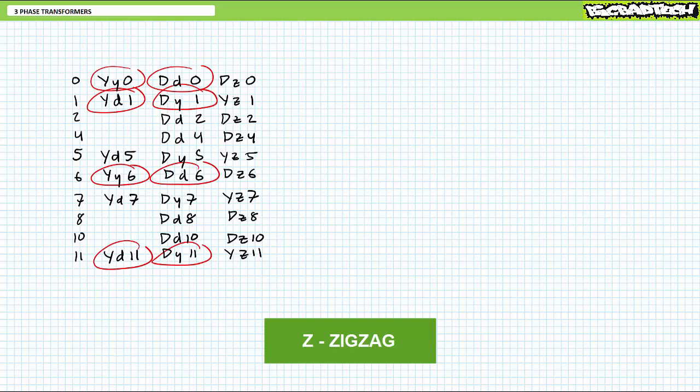Zigzags are kind of like Ys, or if you're an idiot, stars, only they have double the number of windings for each phase such that if you're super, super desperate for a super weird phase shift or an odd voltage magnitude, or you just want to confuse somebody, you can use part of one winding from one phase and part of another winding from another phase to create the desired phase shift and or magnitude. Since this is difficult to describe verbally, it's perhaps worthy of one more illustrated example.